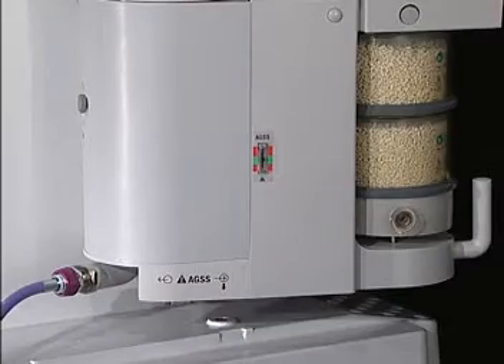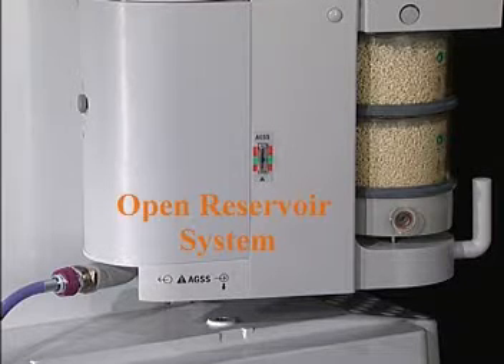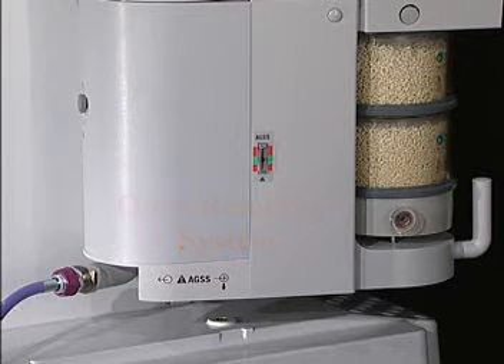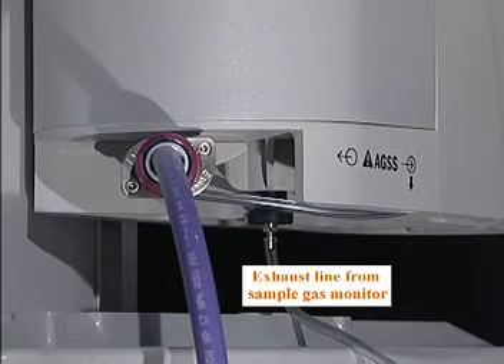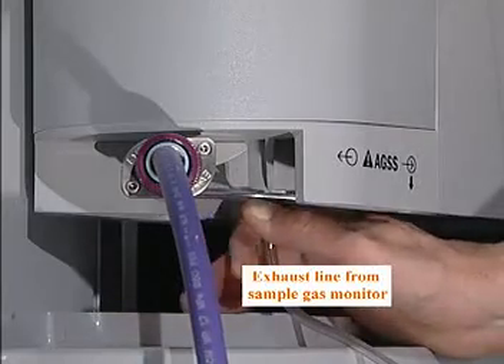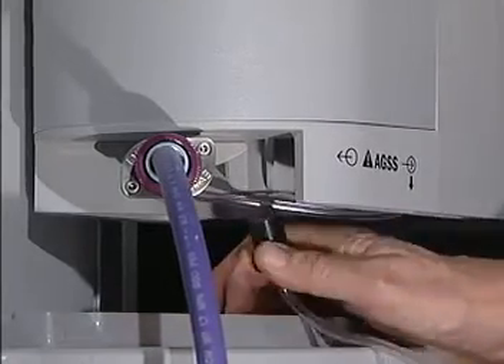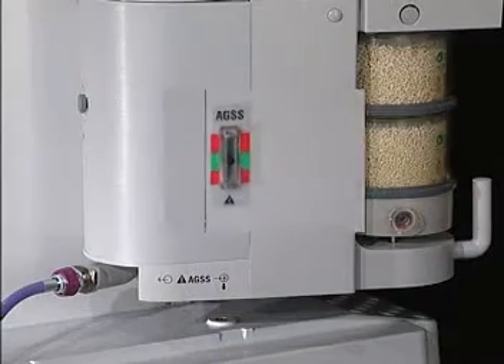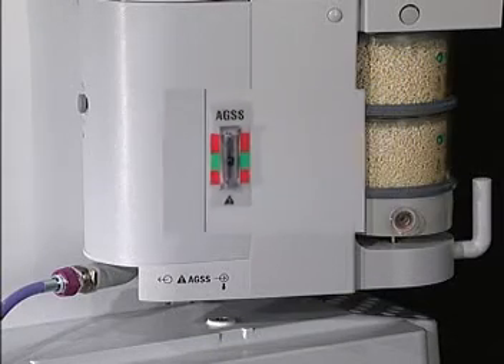There are several scavenging options available for the Anesthesia. If a hospital vacuum source is available, there is an active vacuum option called an open reservoir system, which requires a minimum of 36 liters per minute flow at a minimum of 12 millimeters mercury vacuum pressure. A port is provided for the scavenging of sample gas from a respiratory gas monitor, and a flow indicator is provided to assist in determining the adequacy of flow.